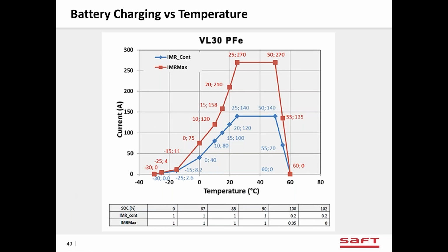This is a look at charging versus temperature. When we're at room temperature, we can take full charge current. This is for our power cell. PFE stands for the power iron phosphate cell. So one string of batteries you could charge at about 140 amps at room temperature. But as the temperature goes down, you have to charge slower.